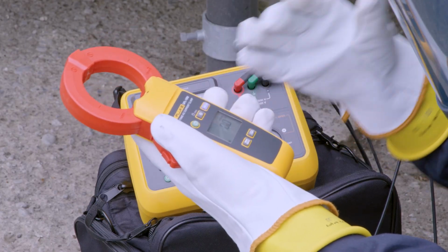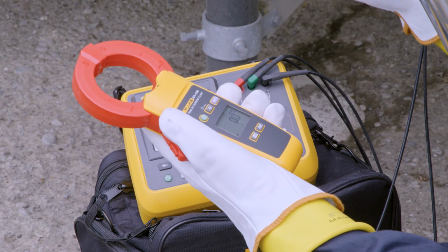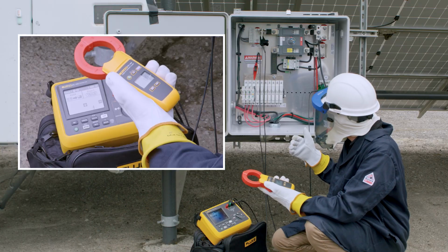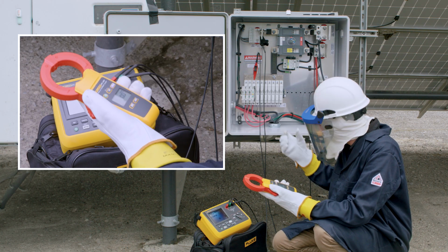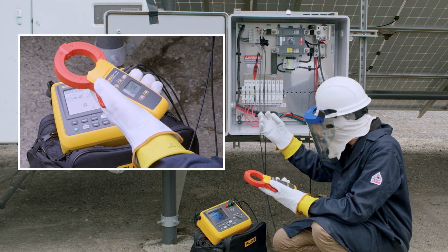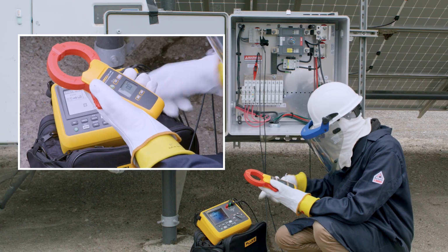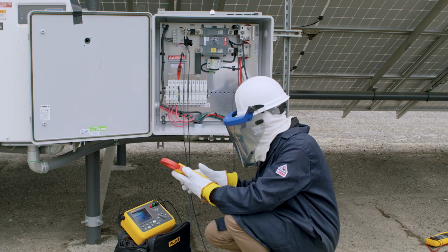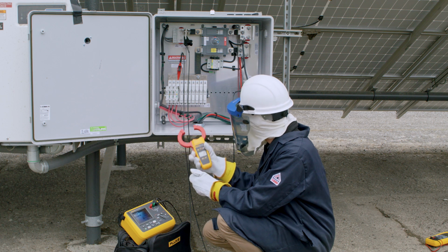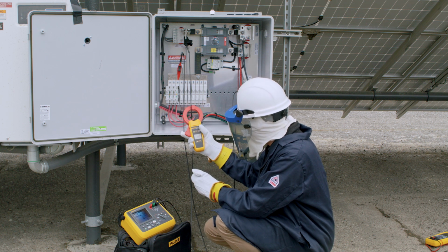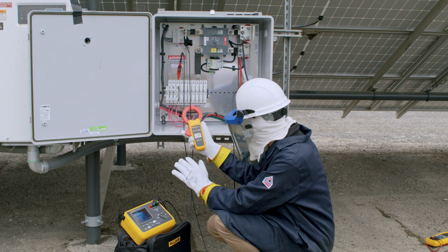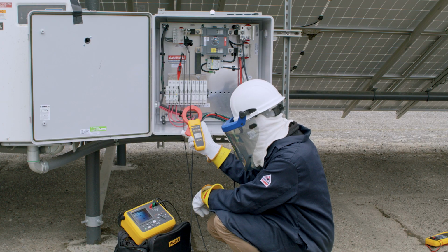So let's take a look at the difference in current measurement between array high, array low, and with the bandpass filter on. I'm injecting onto the negative side because I've got the positive fuses isolated, removed. So I'm going to start by hitting trace so I can put the signal in. If I take my current clamp and put it on my negative lead, I can see in array high, I'm getting about 28.8 milliamps there.